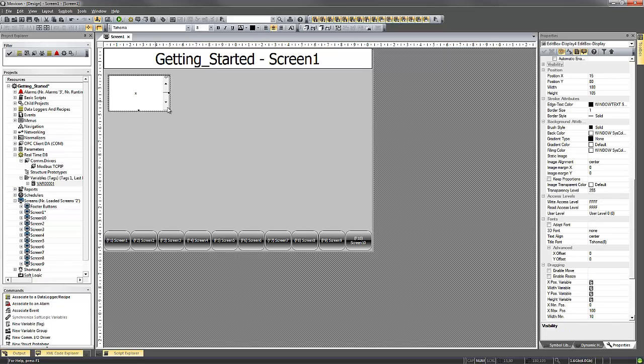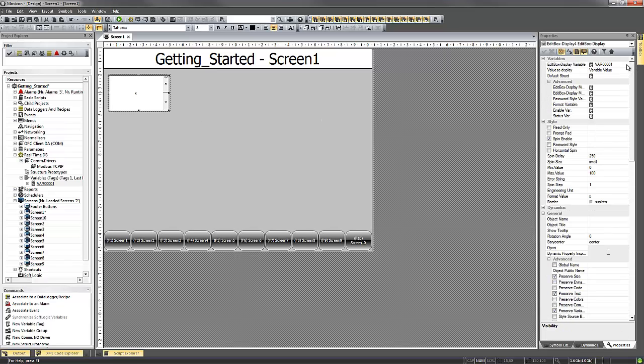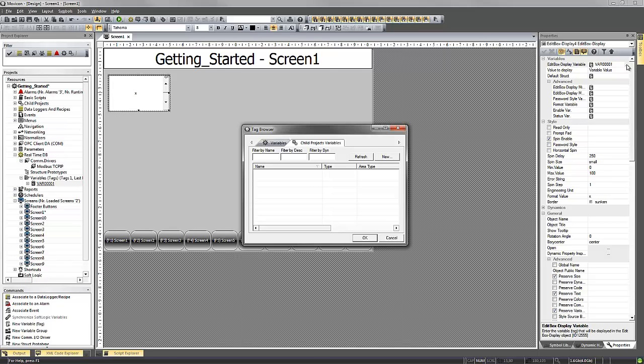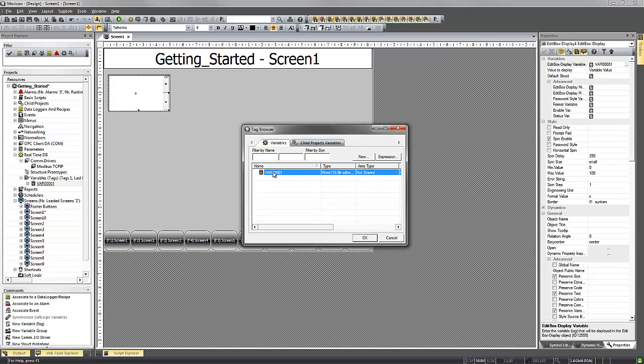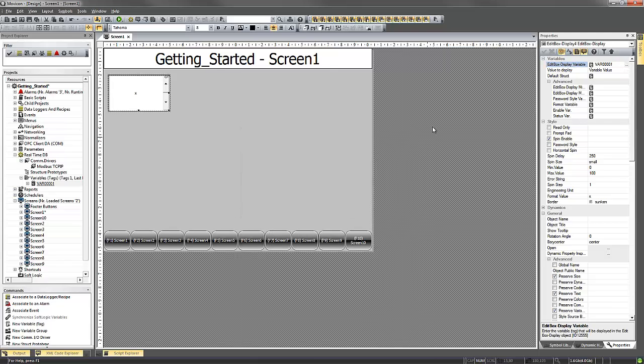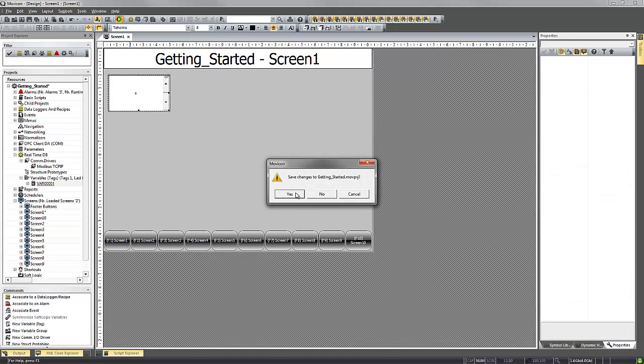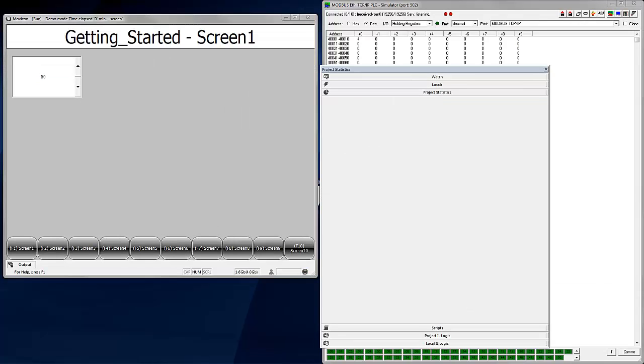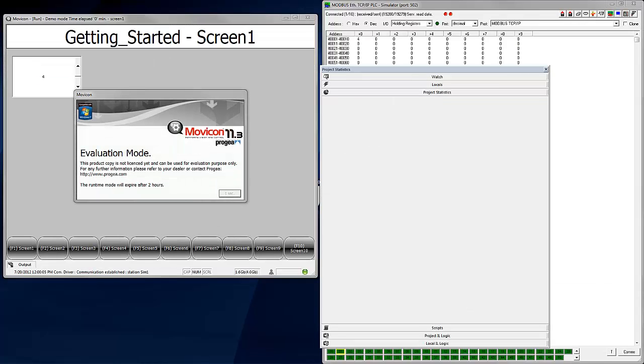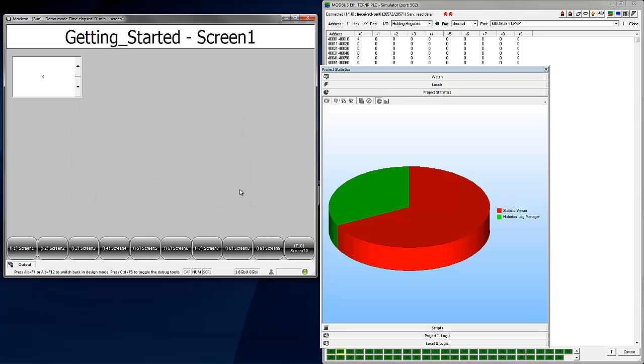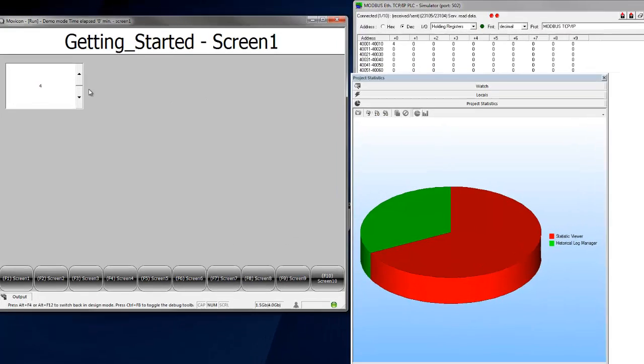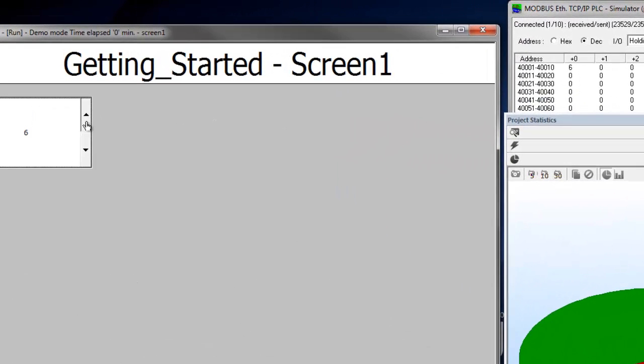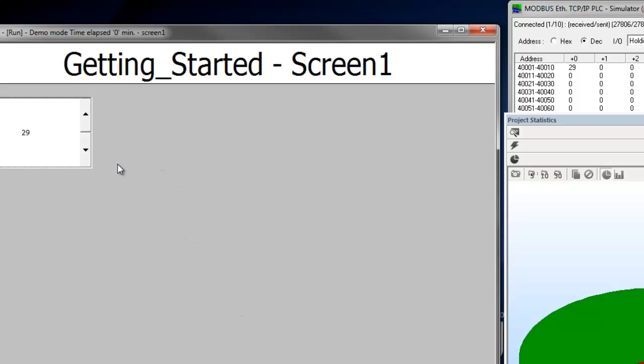Or if you click on the object and look at the properties, you can open up the Tag Browser and find the variable here. And we'll go ahead and test this. In the background you can see the Modbus Ethernet TCP IP Simulator. As they increase and decrease the value, you can see it change. So we know our communications is working and we are configured correctly to our PLC or simulator address.